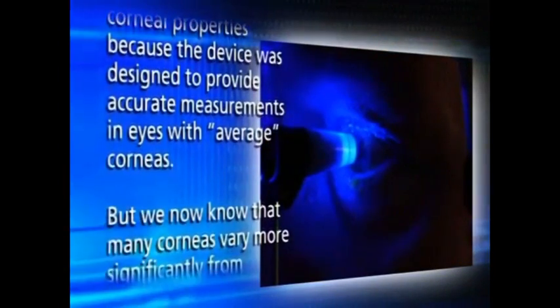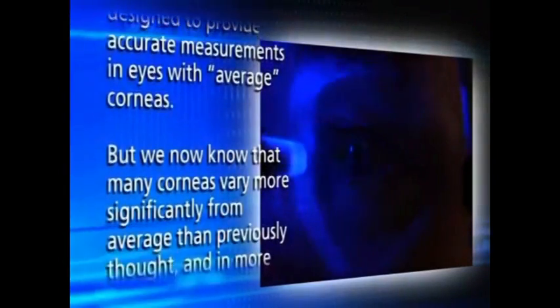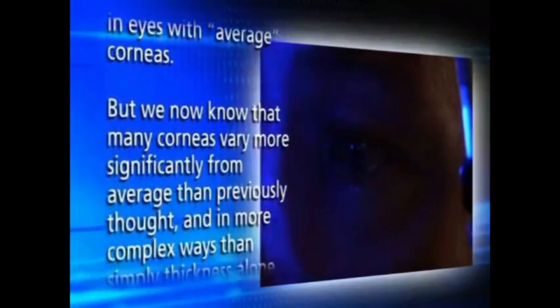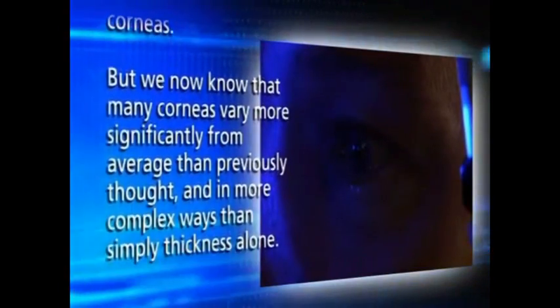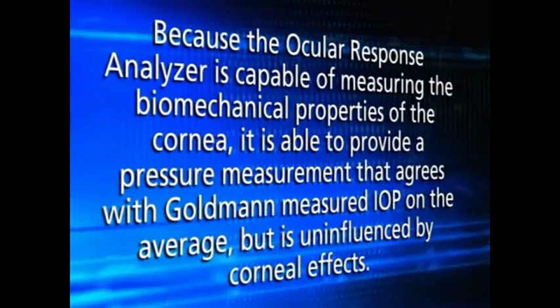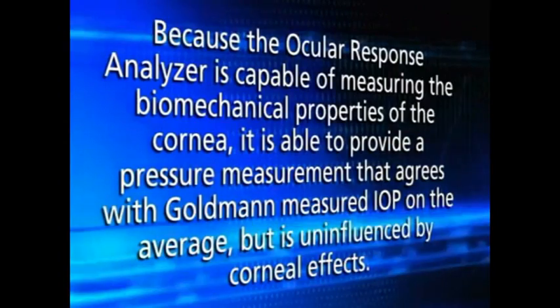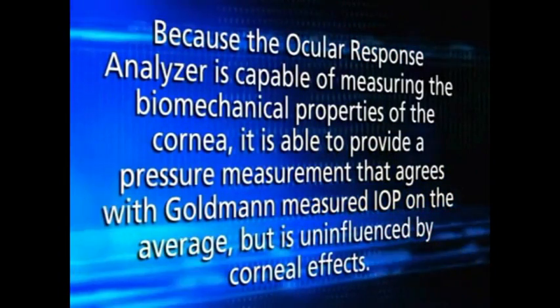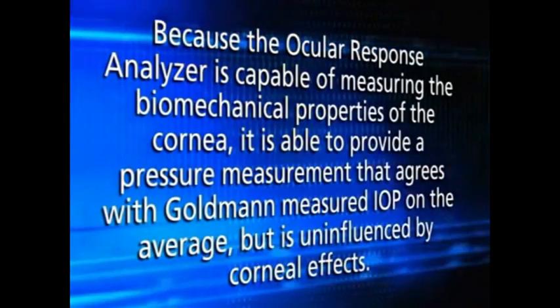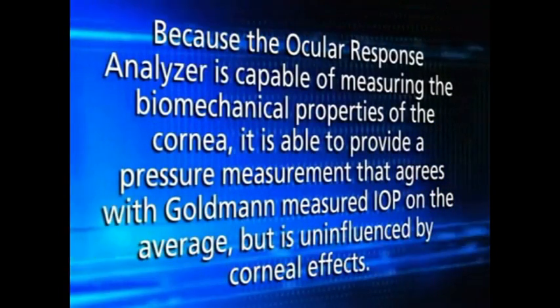But we now know that many corneas vary more significantly from average than previously thought, and in more complex ways than simply thickness alone. Because the Ocular Response Analyzer is capable of measuring the biomechanical properties of the cornea, it is able to provide a pressure measurement that agrees with Goldmann measured IOP on average, but is uninfluenced by corneal effects.